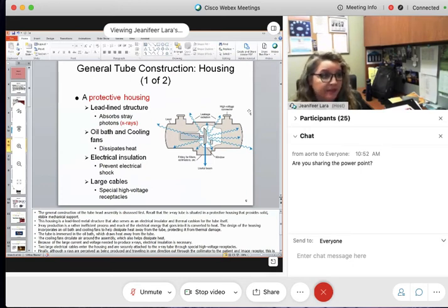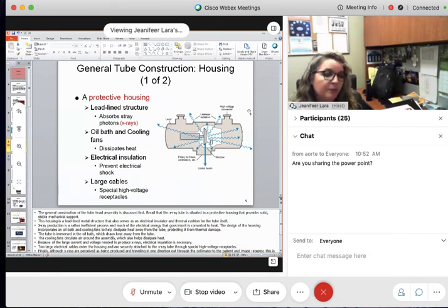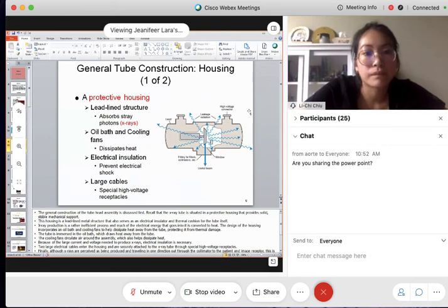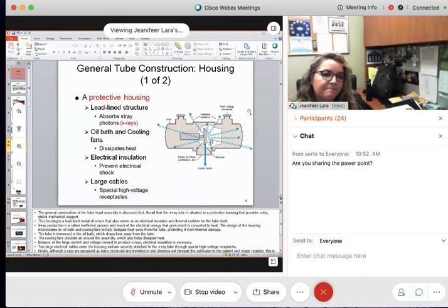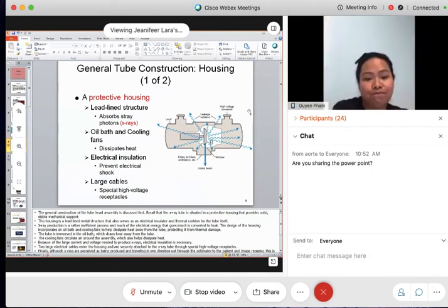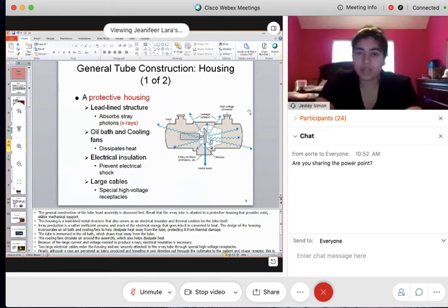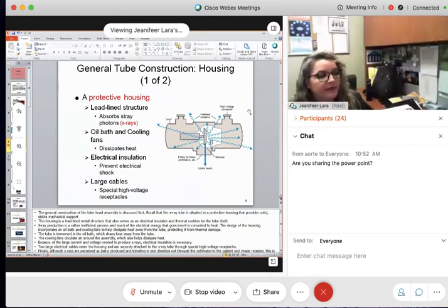The protective housing has a lot going into it. The purpose of being an electrical insulator is to prevent electrical shock. It dissipates heat through oil and through a cooling fan. It prevents photons from escaping because it is lead-lined. And we get that large amount of energy inside the protective housing through large cables with connectors.